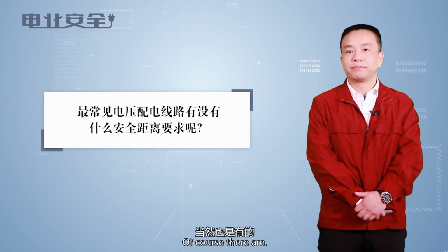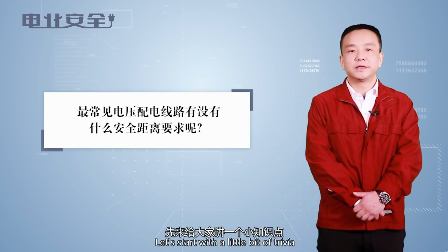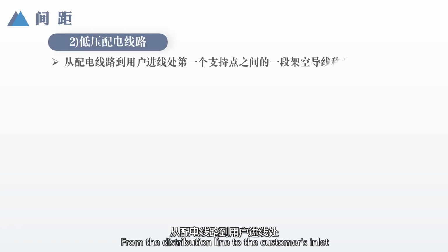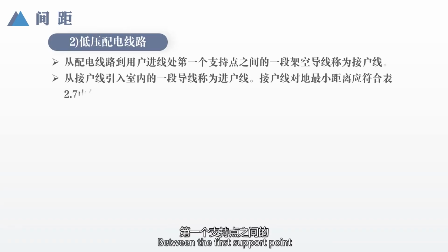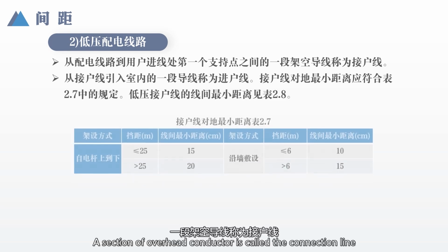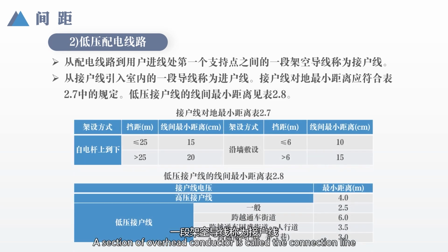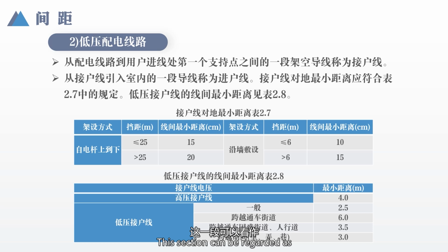Of course there are. Let's start with a little bit of trivia. Household wiring: from the distribution line to the customer's inlet, between the first support point, a section of overhead conductor is called the connection line. This section can be regarded as an intermediate connection between the distribution line and the customer. For example, the minimum distance between the wires of a house connection is generally 2.5 meters.